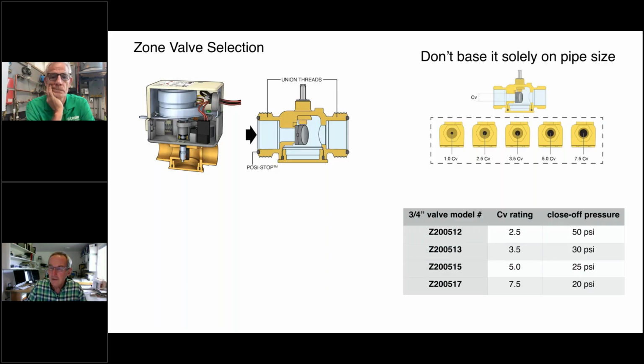But I know Hot Rod has got some valves. Oftentimes we think, zone valves, if I'm dealing with a 3/4 inch copper pipe, I want a 3/4 inch zone valve, and that's as far as the thinking goes. But internally, these valves have different orifices, and they can range from a relatively small hole up to a much larger hole that the flow is going to pass through. And that's going to affect the pressure drop through the valve. Hot Rod, can you hold up one of those valves and just show kind of the differences in that?